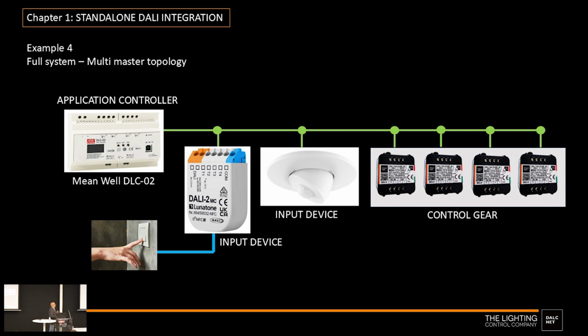Here I'm presenting an example from Meanwell, but there are many others. The main advantage of this configuration is multiple inputs on the system—touch panels, push buttons, sensors. This needs an application controller, usually a device at another level of cost, and some programming that is not only assigning an address, but requires assigning the combination between an event, like a push button press, and an action, like turning on or dimming the lights.